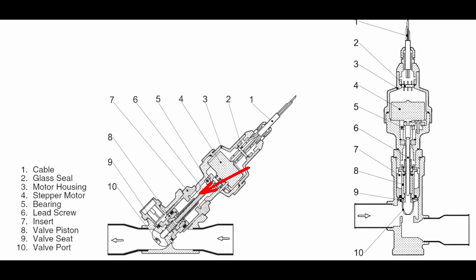But the third and final step to this calibration is it's going to go to a fully closed position. So we start off, we want to fully close. Then we're going to do an open stroke. We want to go full open. Then we're going to go to a fully closed stroke, and we're going to close again. Ideally, at each one of these points, we're going to completely come to a stop, and we're going to hear that valve ticking, right? So that'd be another way to describe it. It's going to have that tick that these will do. That means that it's moved as far as it can go.